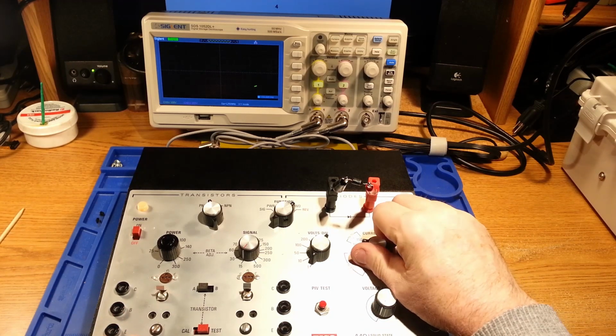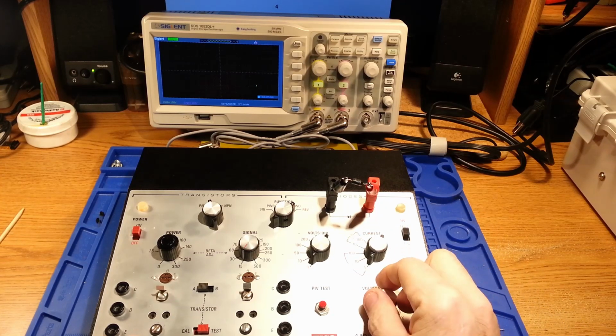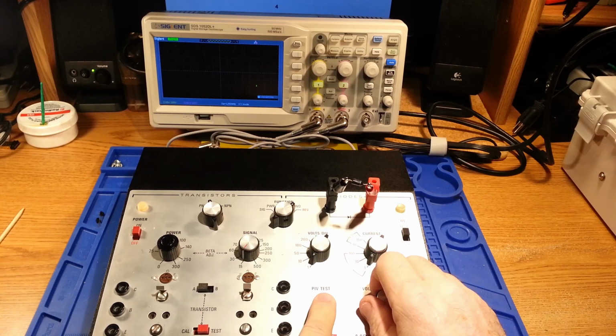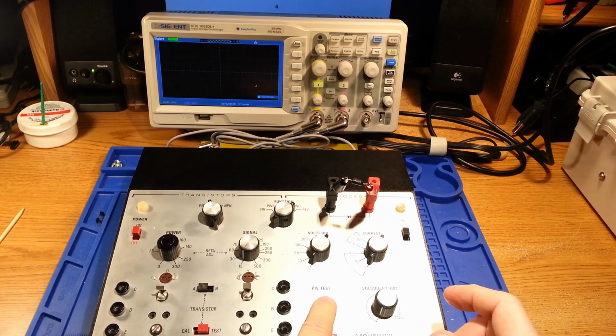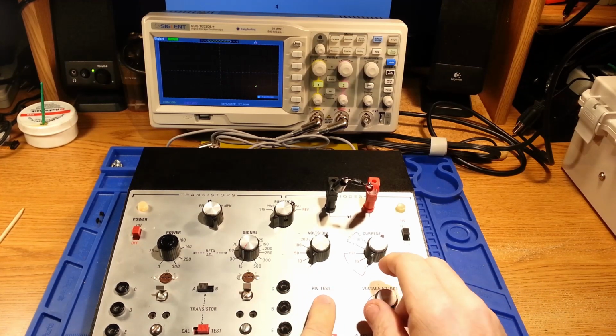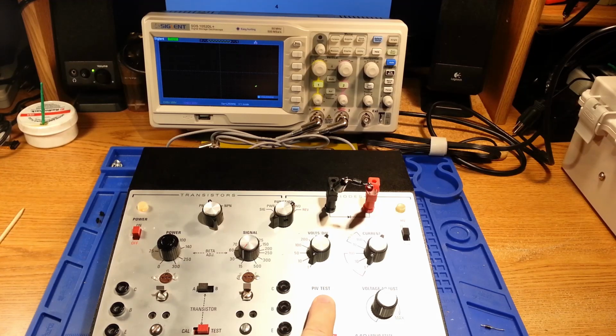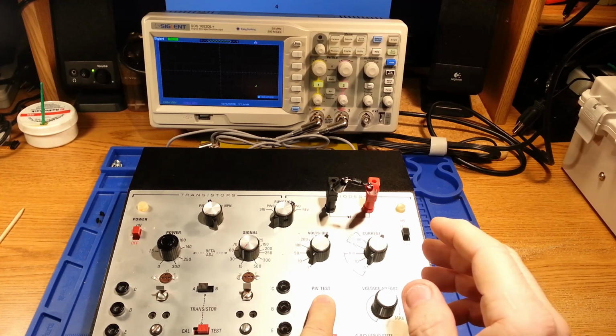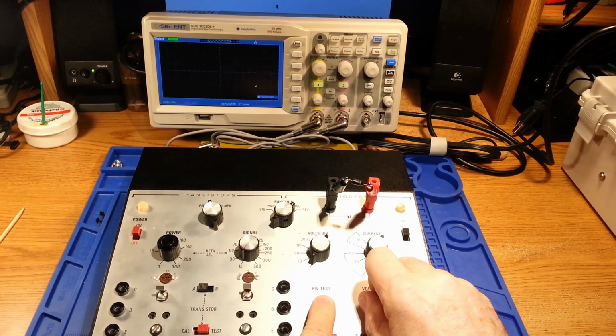So in this case, we're going to check the breakdown voltage of this diode. Now keep in mind, another safety feature of this unit is you have to press this PIV test button. So that makes you always have one hand on this no matter what's going on in order to get the voltage out of it. So it's hard to create a circuit through both of your hands, which is usually fairly dangerous.